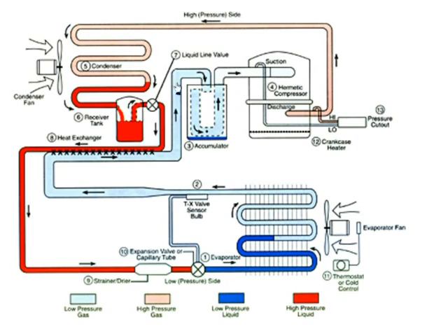Over here, it's the same concept, it's just opposite. You've got a really hot gas now. Normally it's going to be somewhere around 20 to 25 degrees hotter than it is outside. This one really depends on the efficiency of your air conditioner. It's not quite like it is in here. It's harder to come up with a fixed number because it could be 15 degrees hotter than it is outside, or it could be 25 degrees hotter. It really just depends on the efficiency.